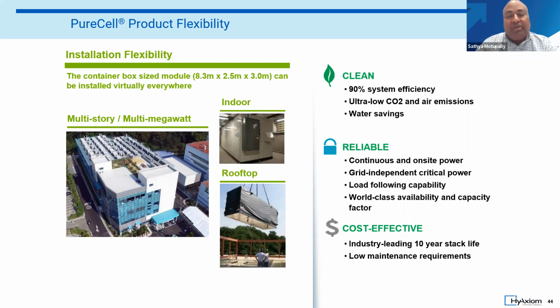Because the fuel cells are simple in their makeup, they have very good reliability. From a cost-effectiveness perspective, especially with natural gas prices high right now—but looking at the average over the past 10 years—if you're able to use the heat, the high efficiency of the fuel cells leads to a cost-effective solution for most applications. Another advantage is flexibility: they can be placed indoors, on rooftops, and stacked in multiple stories to give you multi-megawatts.